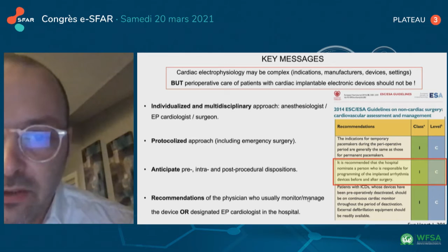We want to avoid adverse events. There are three different categories of adverse events. Of course, the first one is electromagnetic interference that may be responsible for inappropriate therapy, reset mode, magnet mode. The second category is direct damage to the device, to the leads or lead implantation, that may induce an inability to deliver therapy and also alter the battery life of the device. And finally, maybe the most severe is device infection that may be provoked by any type of bacteremia. And we should remember that the prognosis of this type of infection is very severe, with up to 35% mortality.